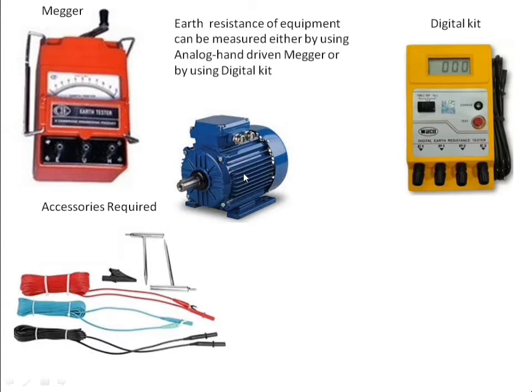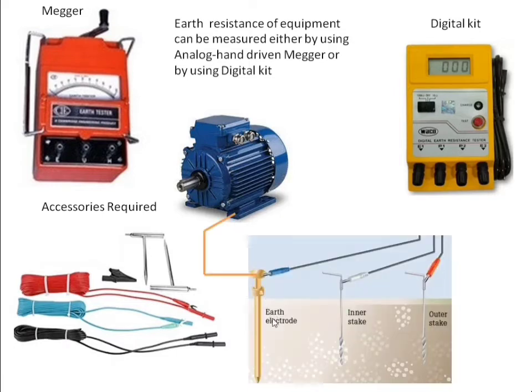This electrical shock is due to the current tending to flow through the physical body of the human being. To avoid this, an alternate path has to be provided by connecting the outer parts of the equipment and ground through a conductor and earth rod. This is shown in the figure. This is called earthing or grounding. Also, to ensure safety, the earth resistance should be very low, less than 5 ohm. This is shown in the picture. The motor is firmly connected to the ground through a conductor and earth electrode, shown in yellow color.